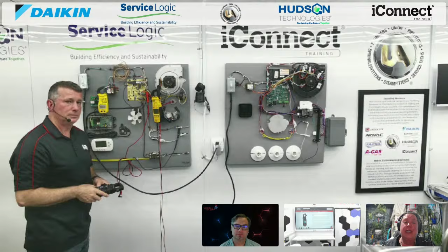Yeah, there's no true RMS rating on it. Right, because we weren't worried about true RMS as much - we weren't working with a lot of those inverter systems where true RMS was really going to play a big feature for accuracy. So meters have come a long, long way. Well, I look at my 579T - that's only a year or two old, it's true RMS, but it doesn't have that Low Z function. So when I'm looking at meters, particularly for the classroom, I think Low Z is an incredibly important feature to be looking for.